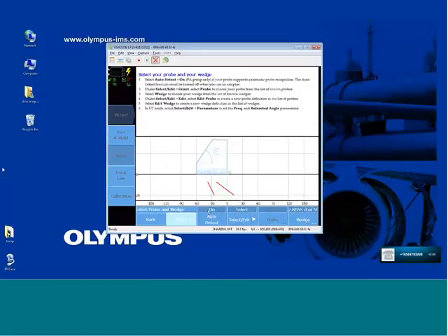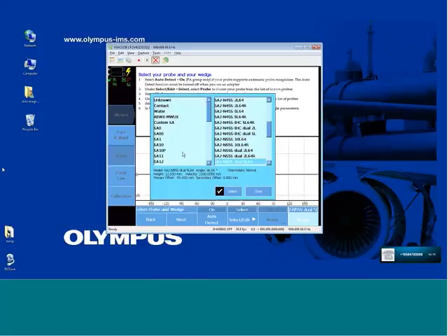Auto detect is on, so we automatically just select the probe. The software knows the probe. We select the family of the probe wedge first, and then the associated wedge for that particular probe here, and the associated information is displayed. Select Next.